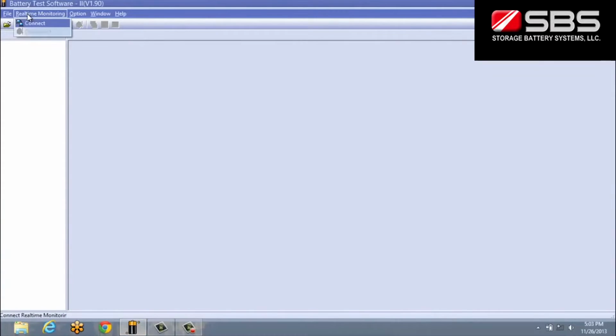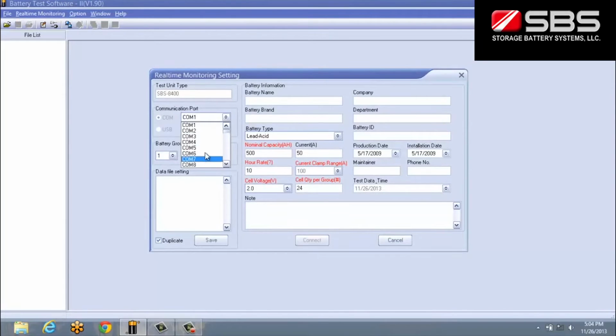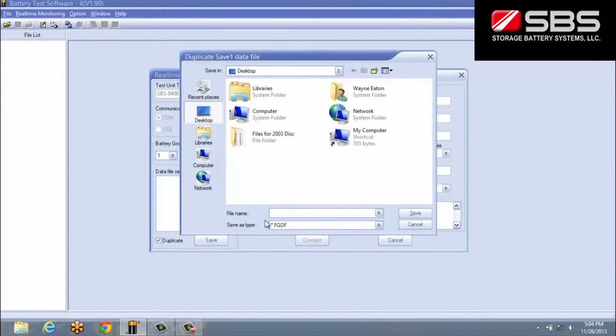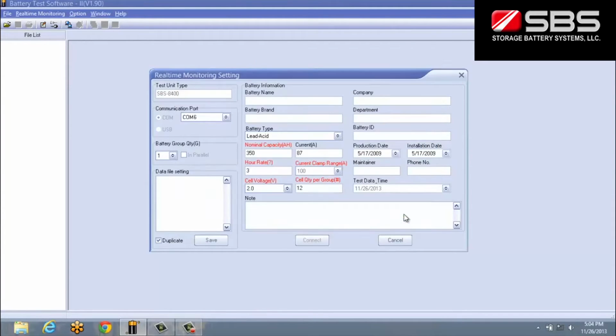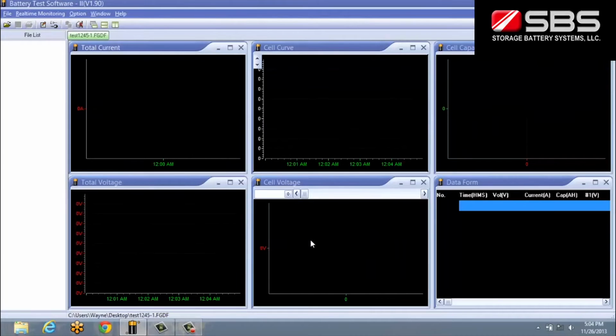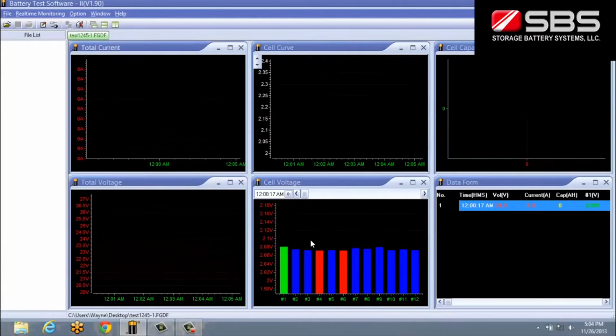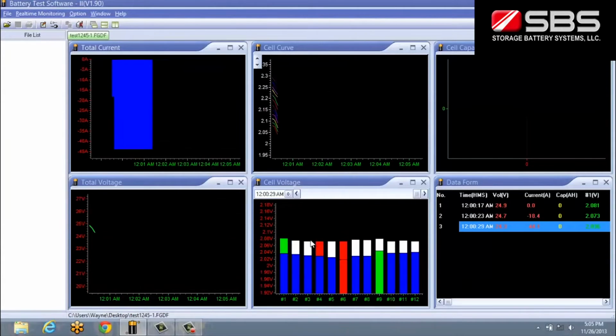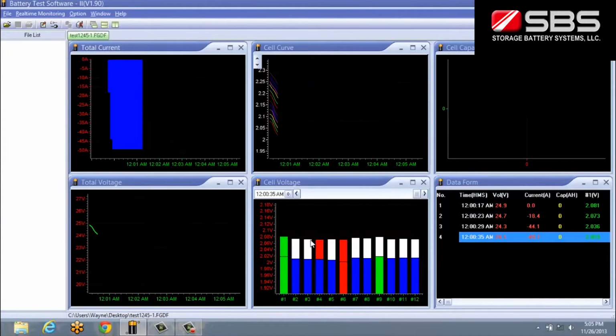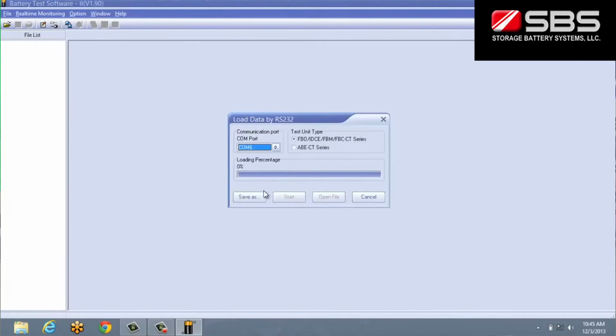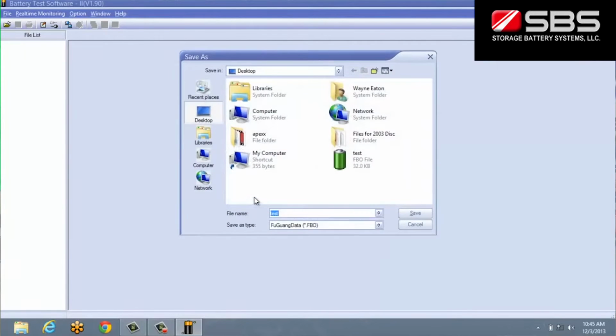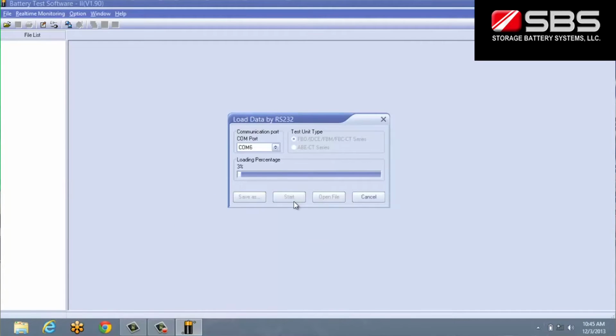To perform real-time recording during testing, connect the RS-232 cable from the main machine with the PC. On the software program, select Connect in the Realtime Monitoring menu to open the real-time monitoring link interface. Ensure that the data in the red highlighted fields is correct for the batteries you are testing, as these are the numbers used to determine capacity calculations. We can now begin the discharge test. The real-time data will be displayed and updated automatically throughout the test and saved simultaneously to a file on the PC. To read data from the unit using the RS-232 connection, select the Read Data through RS-232 button on the menu bar. This will import all of the stored data from the SBS-8400.